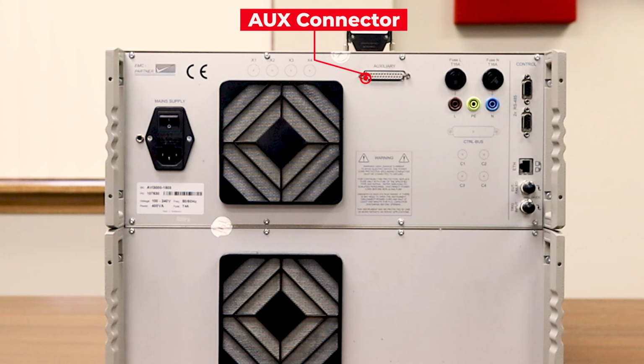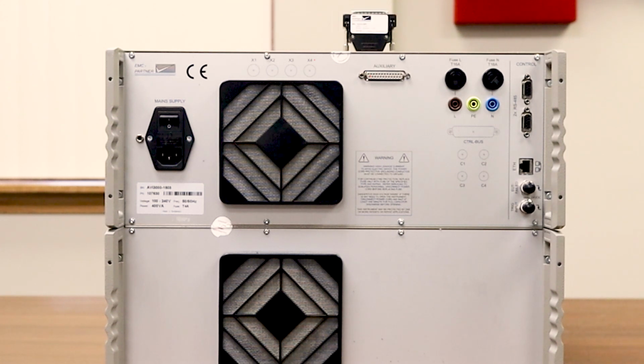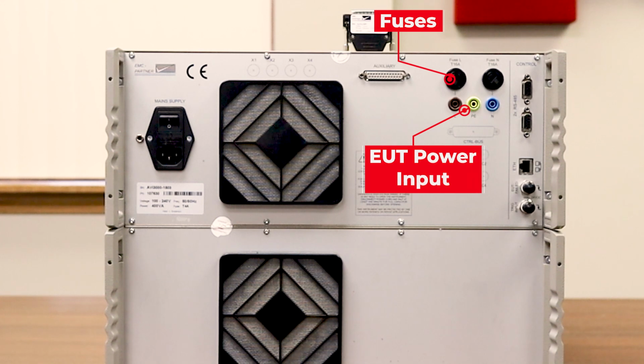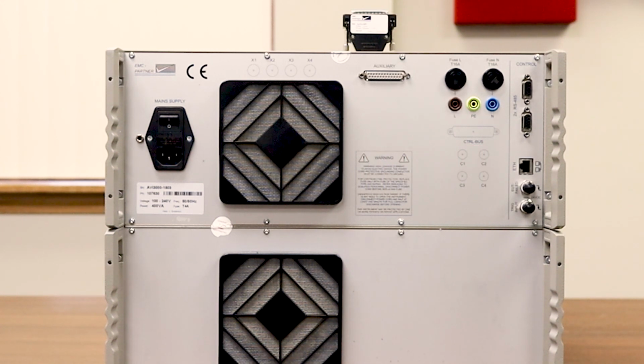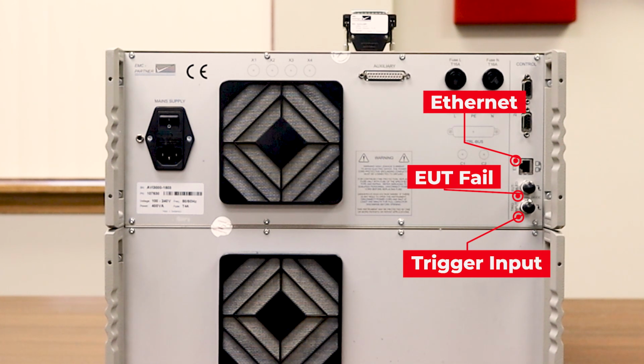As we work our way right towards the center, we have the auxiliary connector. Directly above the auxiliary connector, we have the safety bridge, which will need to be inserted in the auxiliary connector for the system to function. Next to that, we have the EUT power input and fuses. And then finally, all the way on the right, we have our RS-485 interfaces. And below that, we have the Ethernet, EUT fail, and our trigger input.